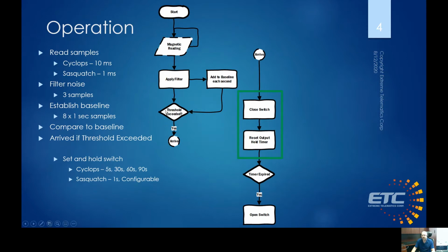So once we've exceeded that threshold and we've determined an arrival, this is how the Cyclops works. We immediately close the switch and we reset the output hold timer. So the hold time by default is 5 seconds. We do have other versions that can hold the output switch for 30, 60, or 90 seconds. So you have to download that special firmware using Vision. But every time a plunger arrival is signaled, we reset that timer. So it isn't necessarily just 5 seconds. If we keep getting arrivals, it will hold it for maybe 6, 7, 10, 20 seconds. As long as the plunger keeps moving, we keep resetting this output hold timer.